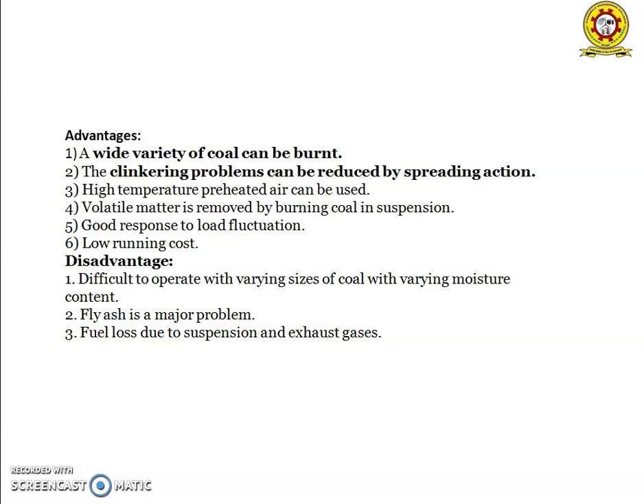Coming to disadvantages: difficult to operate with varying sizes of coal with varying moisture content. Fly ash is a major problem. Fuel loss due to the suspension and exhaust gases. There is a possibility of some of the fuel losses in the clinkers upon the stoker because of the thin fuel bed and suspension burning.